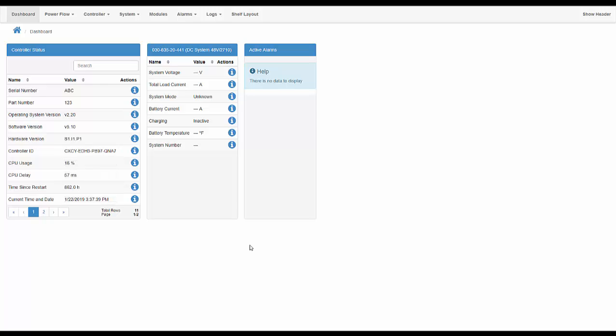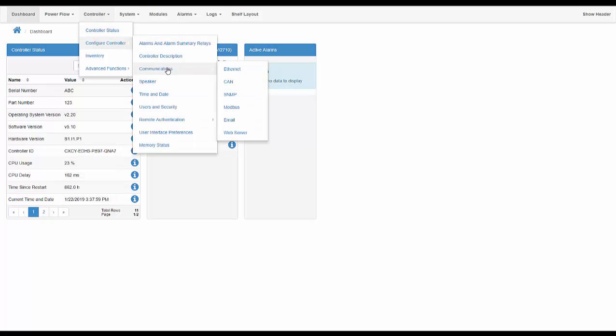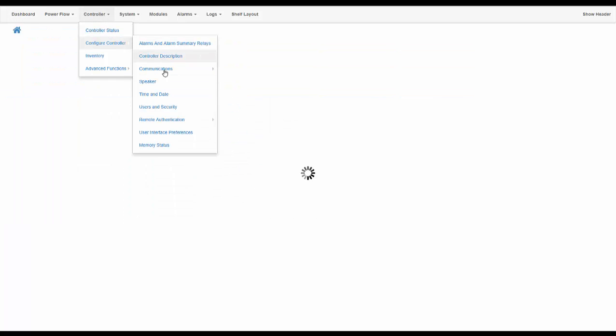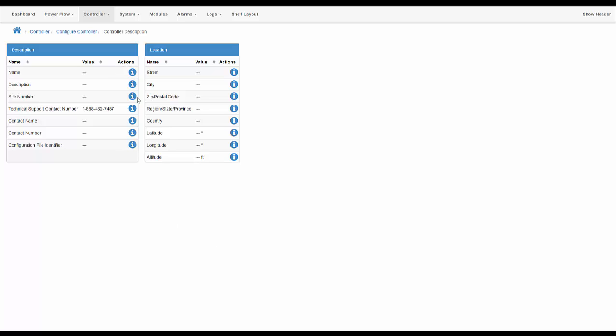A security lockout feature was added to the controller where remote access via the web interface is locked out from configuration or any manipulation of the controller unless a local user overrides it through the LCD interface. As you can see here, as I'm moving around in the configuration section, I am unable to change any of the configuration items because the lockout has been enabled.